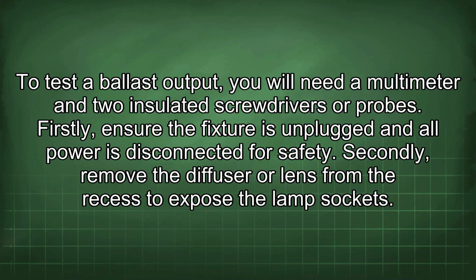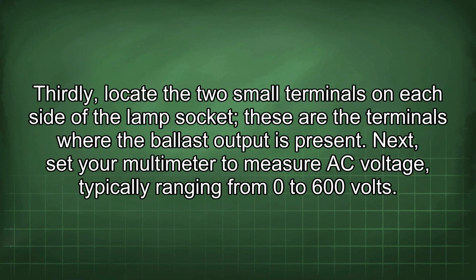To test a ballast output, you will need a multimeter and 2 insulated screwdrivers or probes. Firstly, ensure the fixture is unplugged and all power is disconnected for safety. Secondly, remove the diffuser or lens from the recess to expose the lamp sockets. Thirdly, locate the 2 small terminals on each side of the lamp socket. These are the terminals where the ballast output is present.